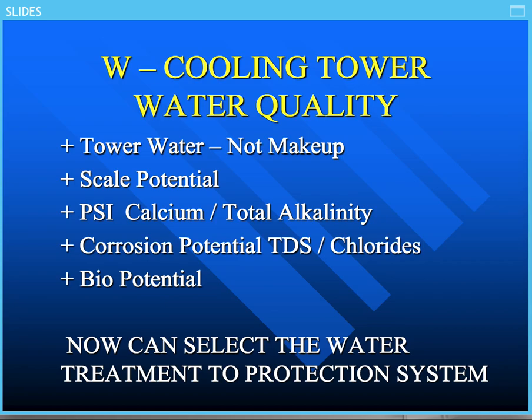I've included one point here that some of you may not be aware of, but by running a PSI, which is calcium alkalinity relationship mainly, PSI is standing for Practical Scaling Index. It actually now has been renamed Puckorius Scaling Index. It's similar to the LSI and the RSI. A lot of people still are using the LSI, which is absolutely incorrect and gives you incorrect information because it uses pH in the water, and you don't need to do that. You can't use pH. You've got to use the calcium alkalinity relationship to determine what the real potential is for scale. And then you adjust your treatment program and your water quality to be able to prevent calcium carbonate or calcium phosphate or even calcium sulfate from occurring.